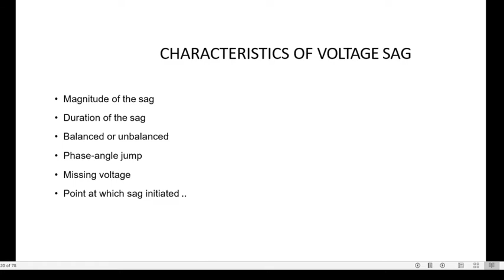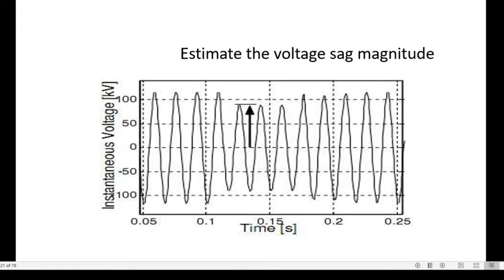So estimating the voltage sag magnitude is done with the help of the power quality analyzer, or we can continuously record the data and plot the graph of the instantaneous voltage with respect to time. And here we can find out the magnitude of the voltage sag, which is defined as the minimum RMS voltage. So the magnitude of the voltage sag is determined from the RMS voltages. The magnitude of the sag is considered as the residual or remaining voltage during the event. The RMS value during the sag is not completely constant, and the voltage doesn't immediately recover after the fault. So there are various ways of obtaining the sag magnitude from the RMS voltage. The best way is use of the power quality analyzer.